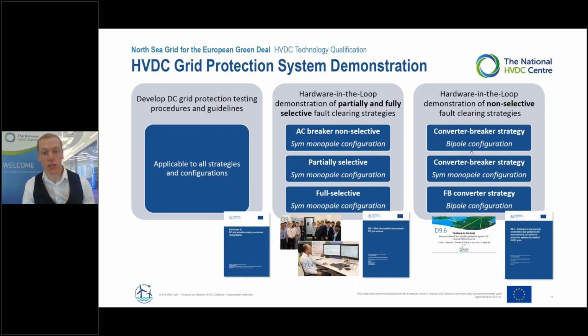So within the work hosted here at the National HVDC Centre, we showed the PROMOTioN IED and Mitsubishi Electric prototype devices in the loop with real-time simulation testing for partially and fully selective strategies. For some of the testing, we were also able to make use of the replica control and protection cubicles we have for the Caithness-Moray-Shetland system, which will be the first multi-terminal scheme in Europe. And as part of all this, we created a benchmark model in RTDS, the details of which can be found in D9.1, and the demos will be available online for you to rewatch on the PROMOTioN website later as well.